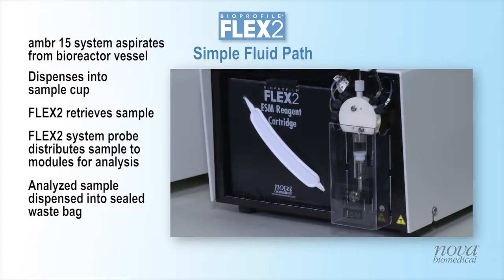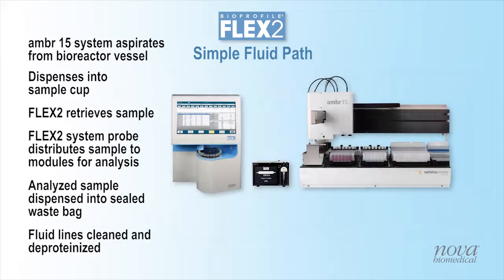Following analysis, the remaining sample is dispensed into sealed waste bags within the ESM's reagent pack. Cleaning and deproteinizing solutions contained within the reagent pack also ensure that fluid lines are cleaned between samples, preventing biological buildup and eliminating sample-to-sample carryover.